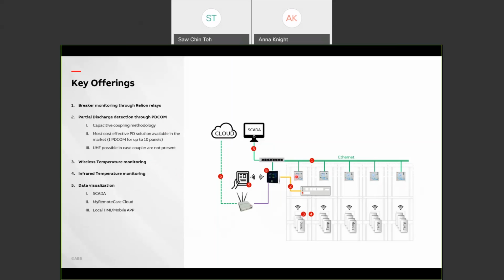The circuit breaker condition monitoring will be done through the protection relays, the 615 or 620 series, and this will then be connected to the SWICOM to do extra analysis of the breaker's condition. For partial discharge monitoring, we have two technologies. We have capacitive coupling technology or ultra high frequency technology. The commonly used one is PDCOM with capacitive coupling technology.